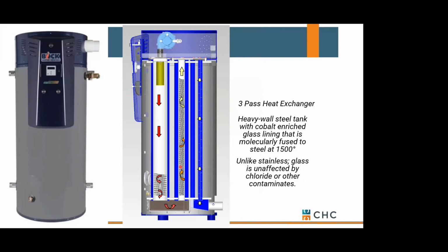Typical on a tank type though, I just wanted to look at this example with Bock. It's a dedicated burner that sits inside the top cap, if you will, and simply sends hot flue gas down the first chamber. That hot flue gas hits some turbulators, additional surface area, comes down to this bottom pan and makes a hard 180 and comes back up for a second pass. Again, it hits a lot of turbulators, and you're dealing with hot flue gas that starts out about 2,300 degrees, comes up to the top here, hits another 180 and comes down these, how do I say it, third pass tubes before it exits or vents the water heater.